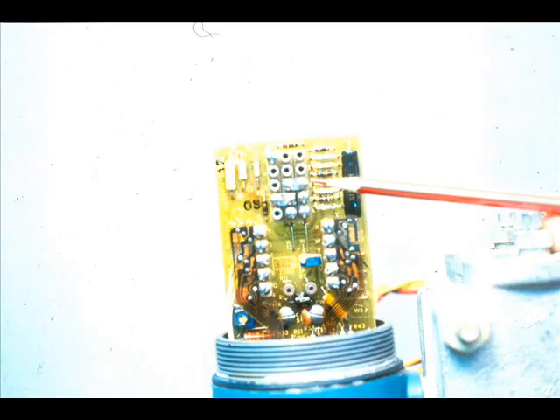Like the Delta P to I transmitter, the limit of suppression and elevation is determined by the circuit board used. An add-on kit is not necessary for suppression or elevation. The suppression or elevation adjustment is made with the zero adjustment.